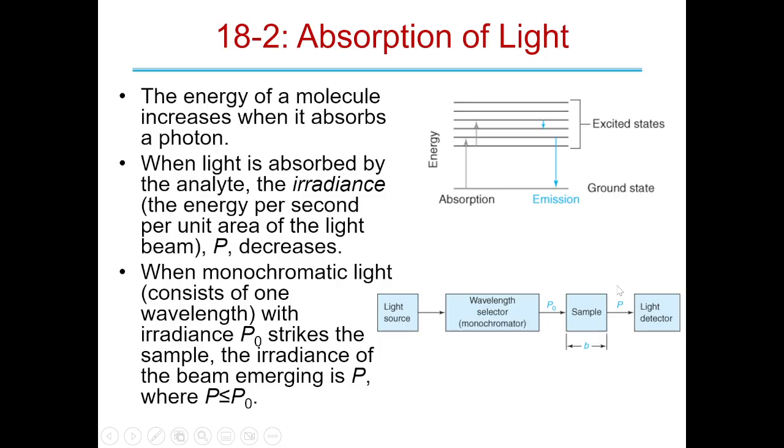Sometimes you do these measurements. You'll have a P0 that you think is right. You'll measure the P output, the irradiance output, and you will get a number that's higher. Do you know what that means? You can actually use it for things.